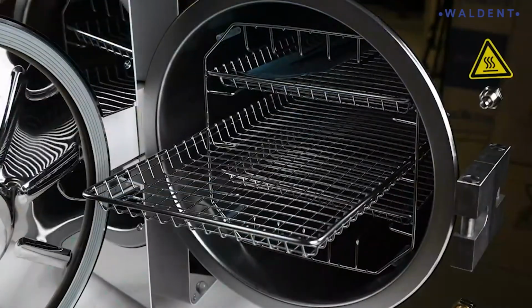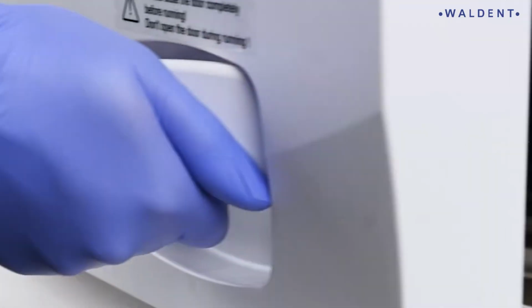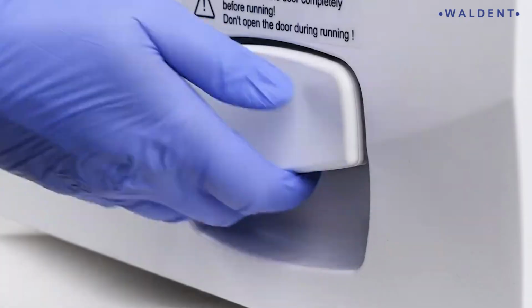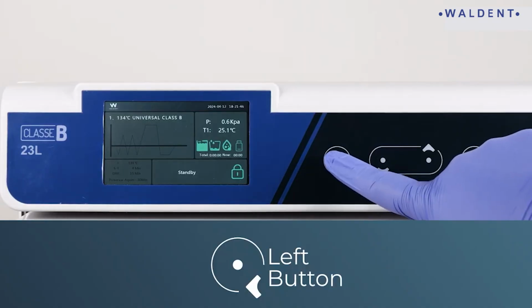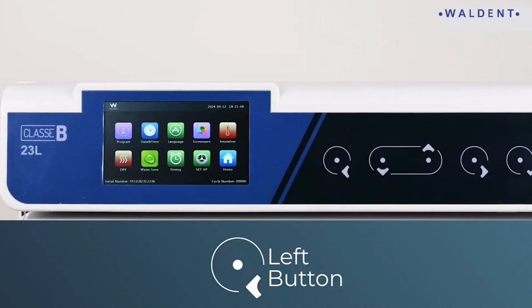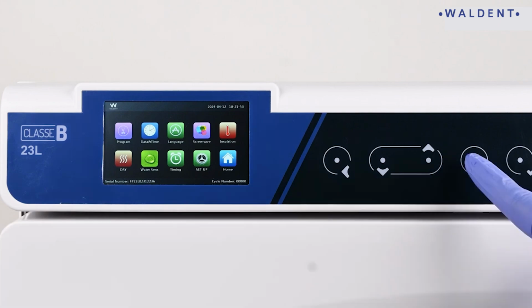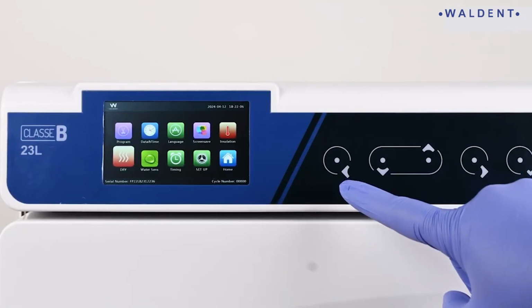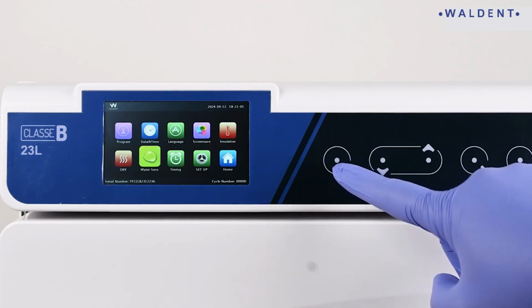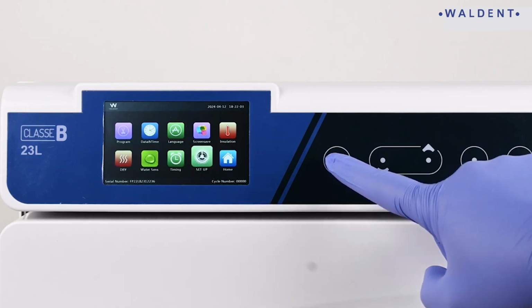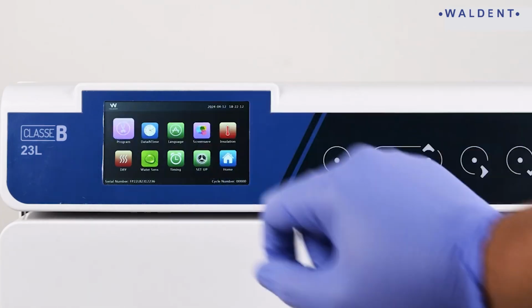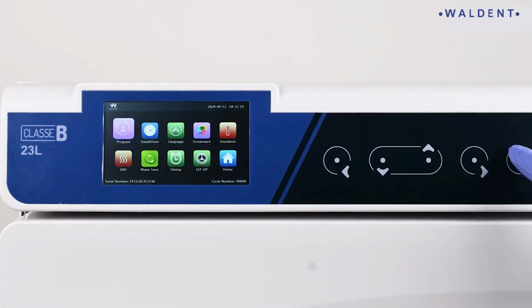Open the door and place instrument securely in the chamber. Remember, do not open the door during the sterilization cycle. Press the left button to enter the main menu. You will see 10 icons: Program, Date and Time, Language, Screensaver, Insulation, Dry, Water Sense, Timing, Setup, and Home. Select the program icon and then press the confirm button.